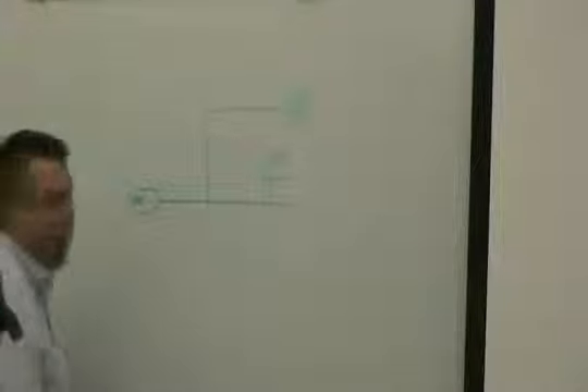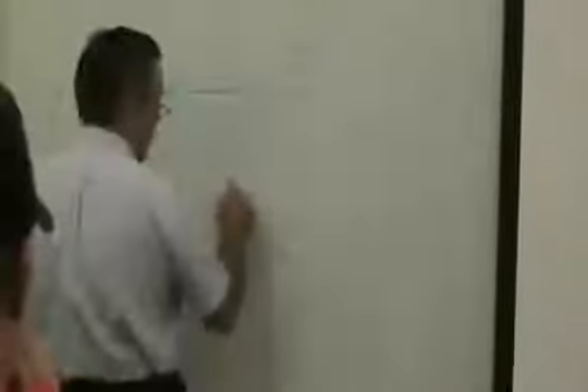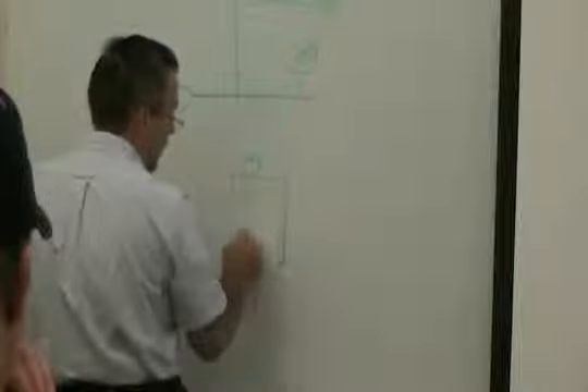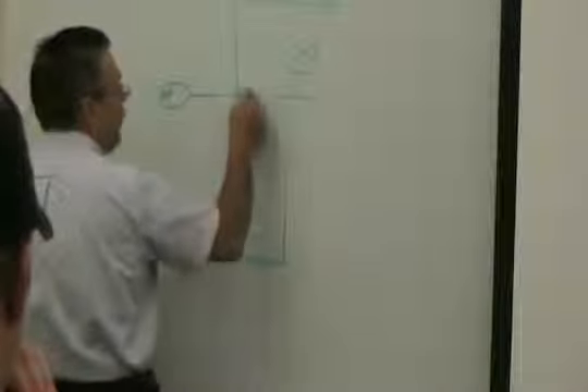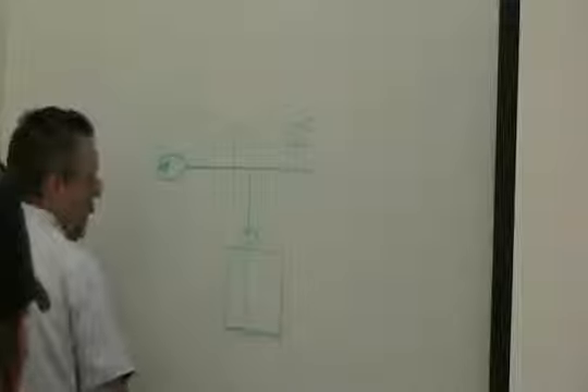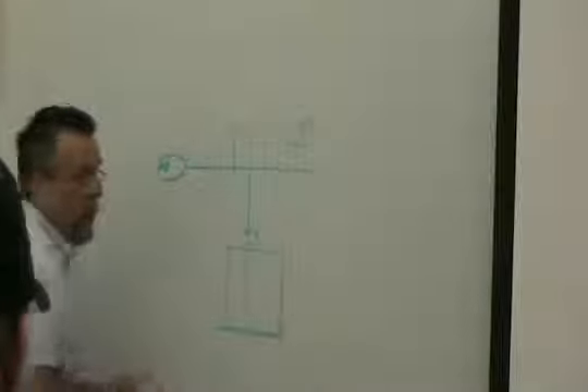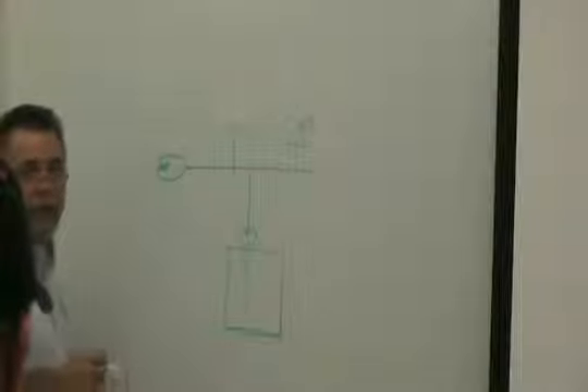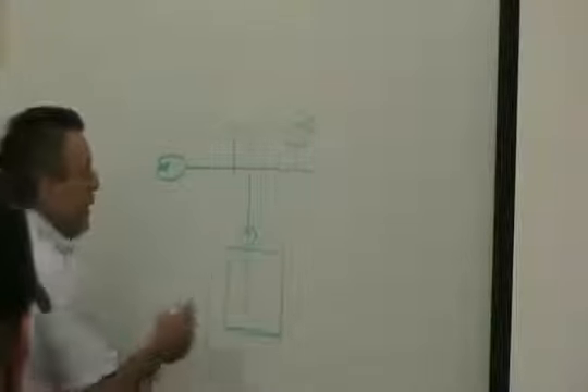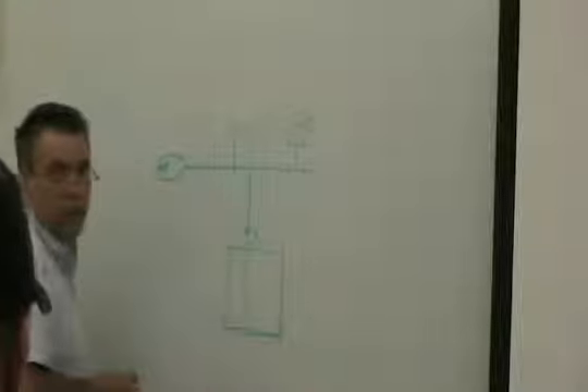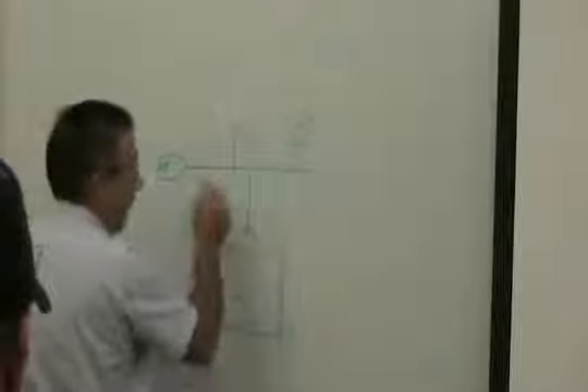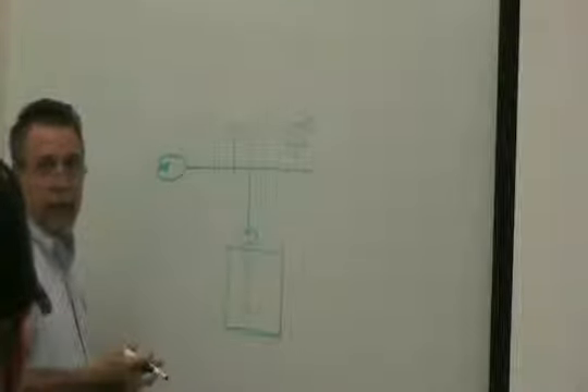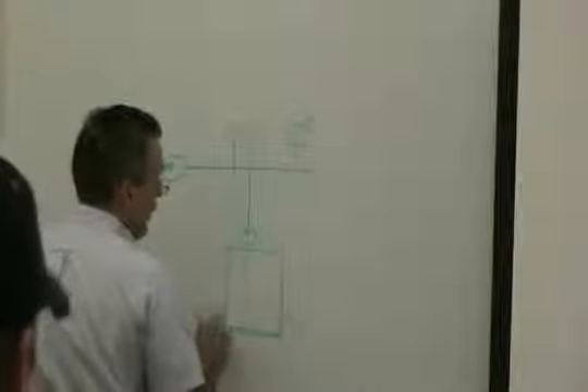Well, in a glycol system, you don't really want a direct connection. So in a glycol system, there are little package systems that maintain your glycol in a tank. And then you have a feeder pump that actually feeds the glycol into your system. And this would go away. So this generally would have to go at the top of your building because you can't generate any static pressure. You can do it like this, but you don't have anything to make up that minimum static pressure in your system. So this would go at the top of the building.